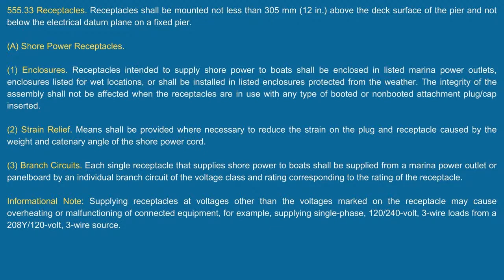But if you want to call it an individual branch circuit—another interesting point, somebody said, well, if you go look at 422.16 B43, it says you can have an individual branch circuit. And I said, exactly, but you left out the most important part: what is that individual branch circuit feeding? It says a receptacle. And a receptacle is going to be put at an outlet, which is the box.